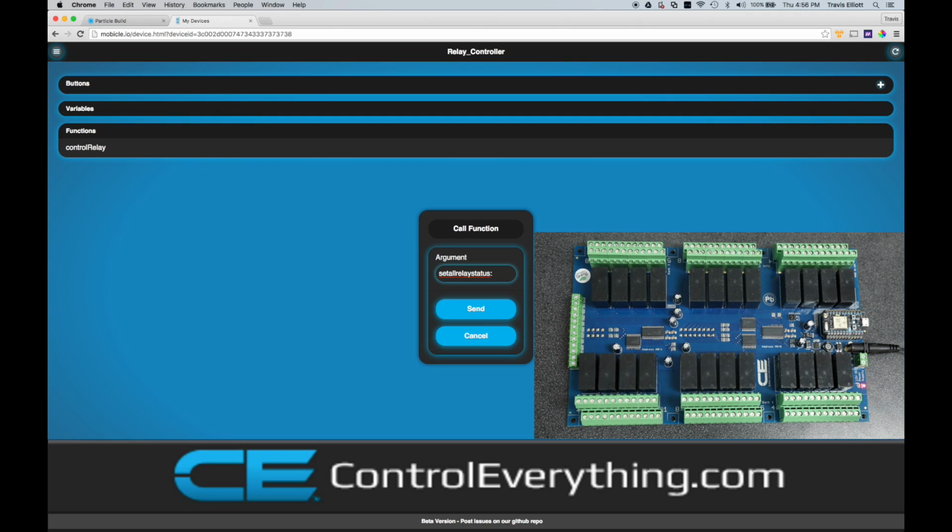Note that if their bit value is not set in this byte and they were currently on, they will turn off. So let's use a command to turn on relay 1 and 8 in bank 1. That would be indicated by adding the bit values of 1 and 8 together. So that's going to be adding 1 and 128 together. So we'll enter 129, and that's going to set relays 1 and 8 on in bank 1.